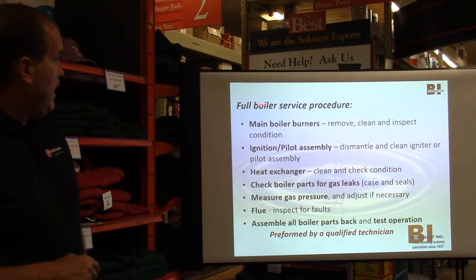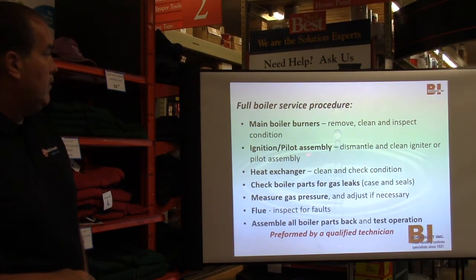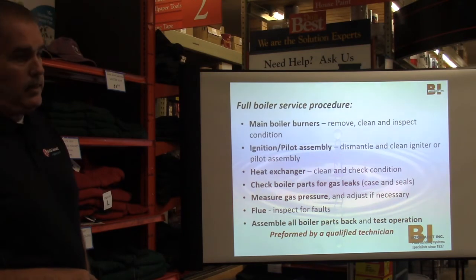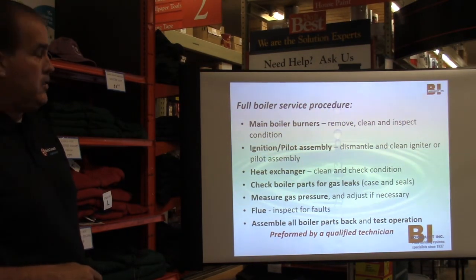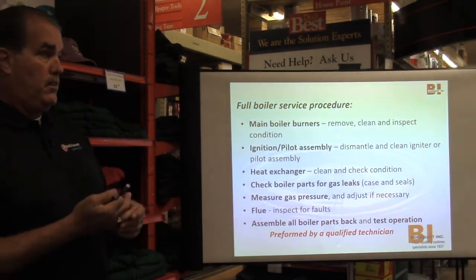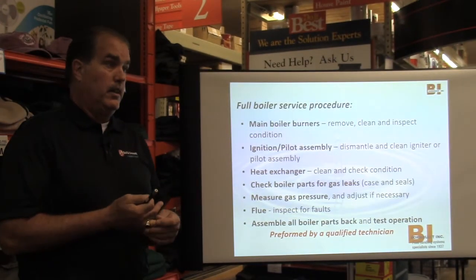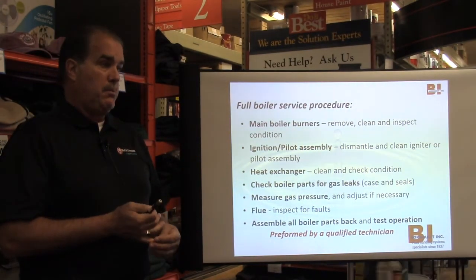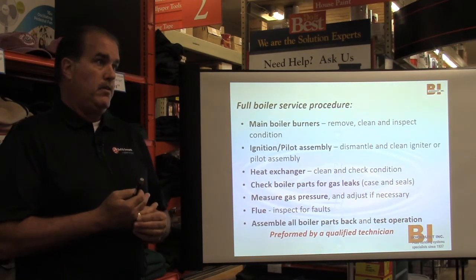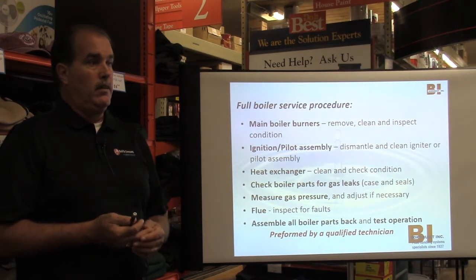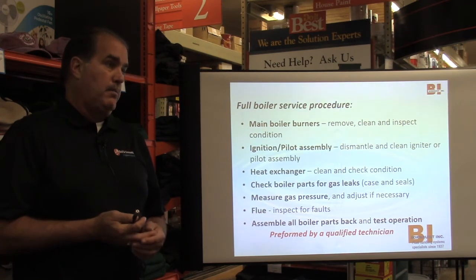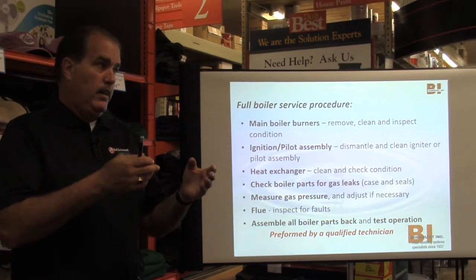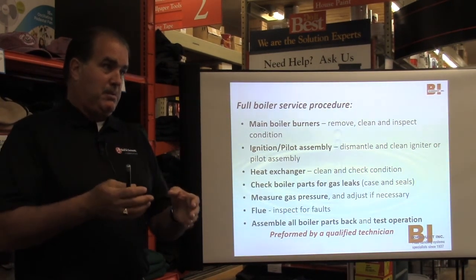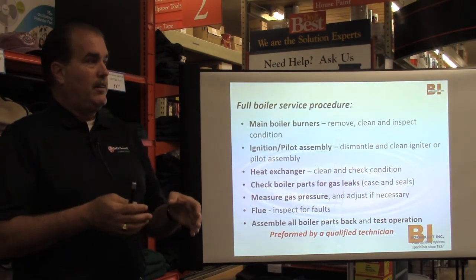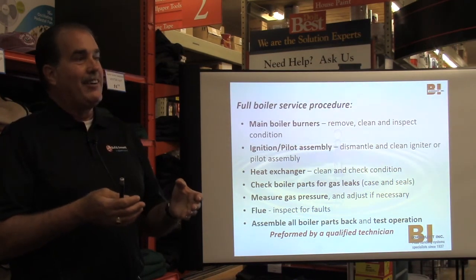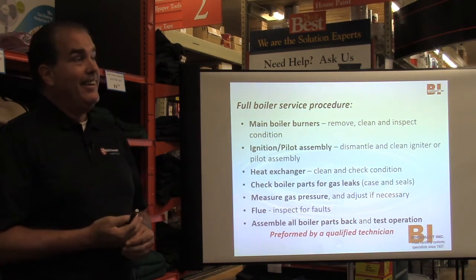And on modulating boilers, or even atmospherics, he's going to be checking your pilot light. He's going to be checking your igniters. Some boiler makers recommend replacing them annually. Residential, not as much. Commercial, more, where you actually go in and replace the igniter or the flame rod annually. So if you really think about it, compare that expense to replacing it on Christmas Eve when the boiler goes out, because it always goes out on Christmas Eve. Now you're really going to pay.